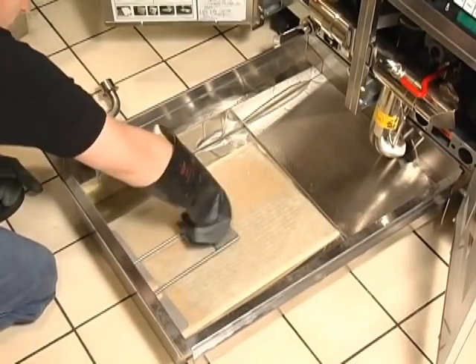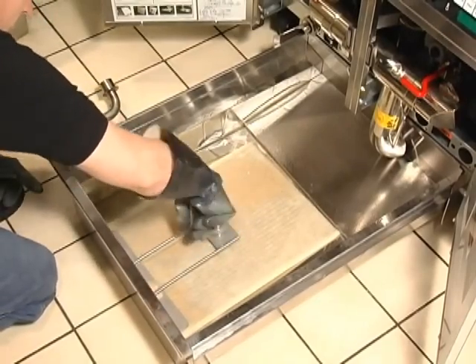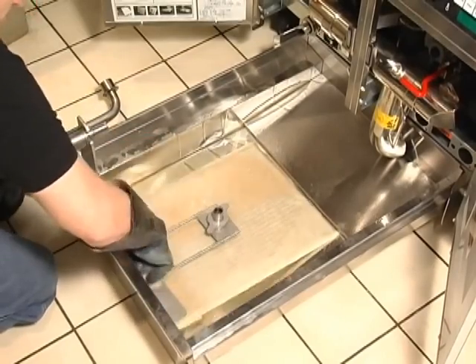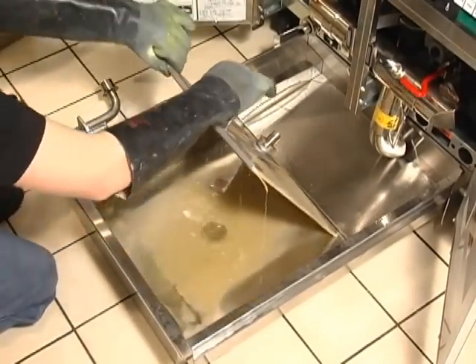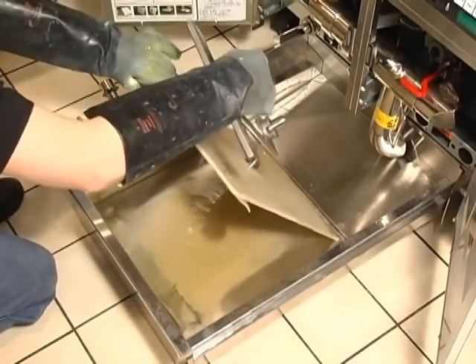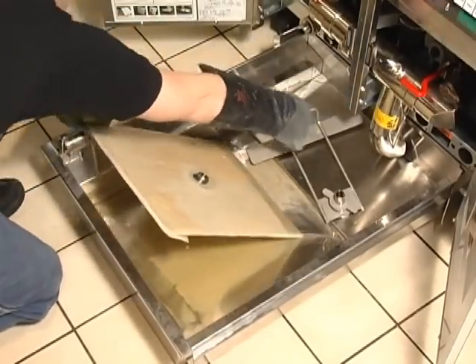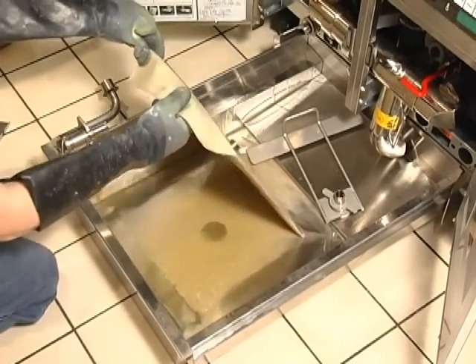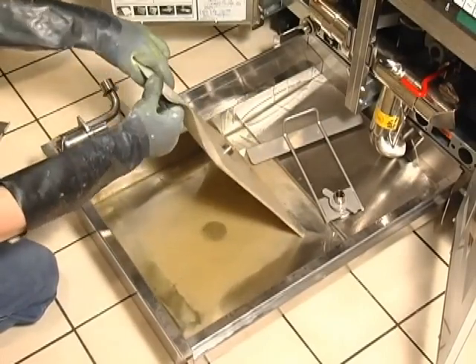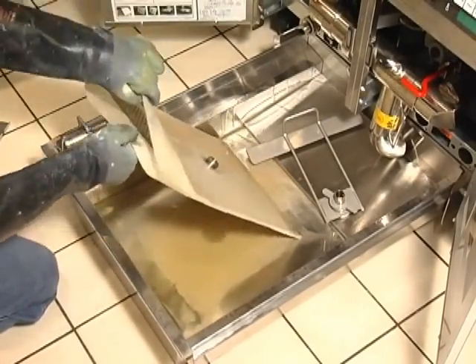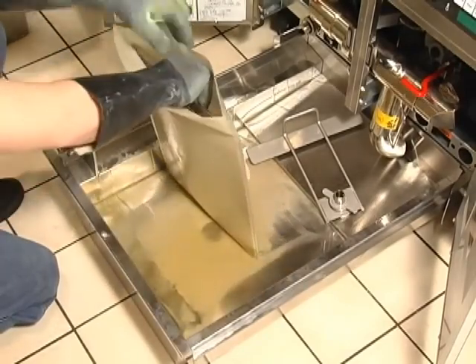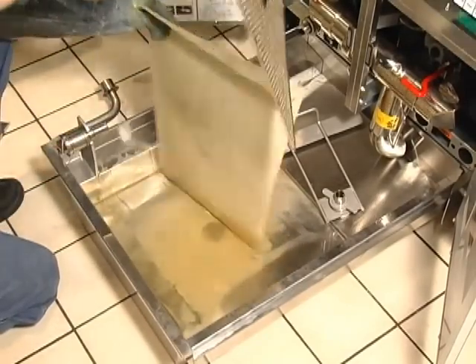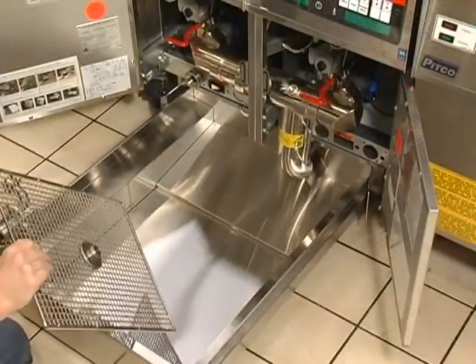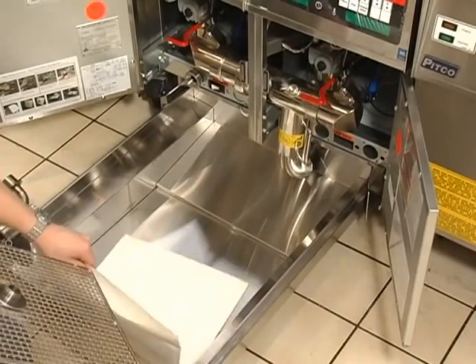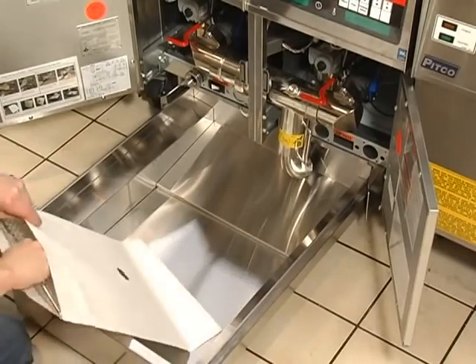Pull off and swing over the pickup tube. Loosen the lock nut in the center of the paper assembly. Remove the paper retaining clip from the paper assembly. Open the paper envelope and remove the support rack. After cleaning the pan and filter components, slide the support rack into a new filter envelope.